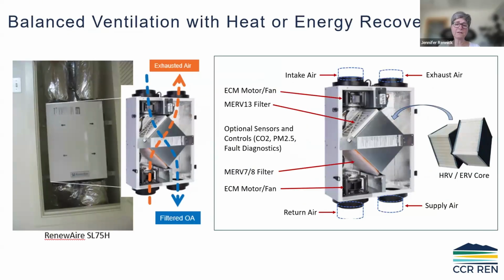The other thing that's new to the code is there are some requirements now specifically around balanced ventilation with heat or energy recovery. And we're finding that not everyone really knows what balanced ventilation with heat or energy recovery is. So I included this diagram. Essentially, this ducted fan system brings fresh outside air into the space, and as air is exhausting out of your home or your small office, fresh air is coming in, and the heat or the energy can be transferred so that the air coming into the home is essentially tempered. So it doesn't come in super cold or super hot. And some energy efficiency is there.